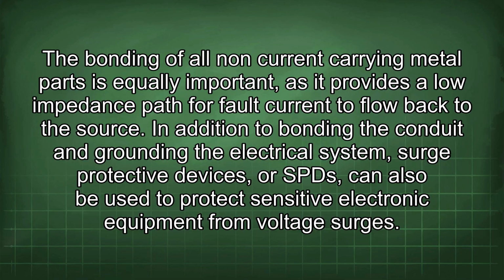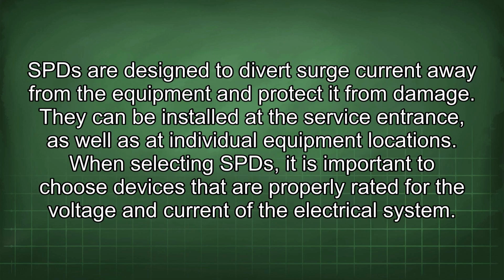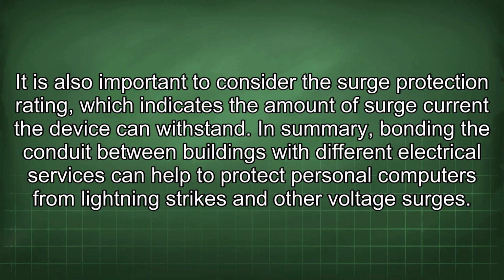In addition to bonding the conduit and grounding the electrical system, surge protective devices, or SPDs, can also be used to protect sensitive electronic equipment from voltage surges. SPDs are designed to divert surge current away from the equipment and protect it from damage. They can be installed at the service entrance, as well as at individual equipment locations. When selecting SPDs, it is important to choose devices that are properly rated for the voltage and current of the electrical system. It is also important to consider the surge protection rating, which indicates the amount of surge current the device can withstand.